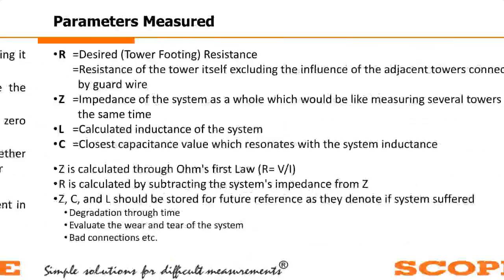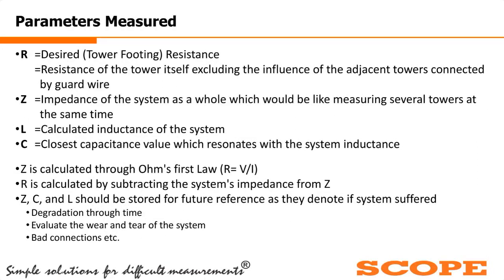As I have explained, these are the connections. In this tower footing resistance meter, generally four parameters are measured. First one is R, the desired tower footing resistance, which is a calculated value. Then the next is Z, the impedance: the total impedance of the overall electrical system is measured, and R is the calculated value. Then L is the calculated inductance of the system, and C is the closest capacitance value due to the adjacent tower. So these four parameters are measured by this tower footing resistance meter.